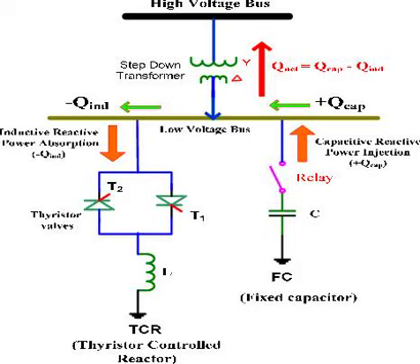An SVC operates by dynamically adjusting its reactive power output to either absorb or generate reactive power. Reactive power is essential for maintaining voltage stability in power systems but does not perform any useful work. The SVC uses thyristor-controlled reactors and thyristor-switched capacitors to achieve this control. By regulating reactive power, an SVC can help balance the system voltage, mitigate voltage fluctuations, and enhance power transmission efficiency.